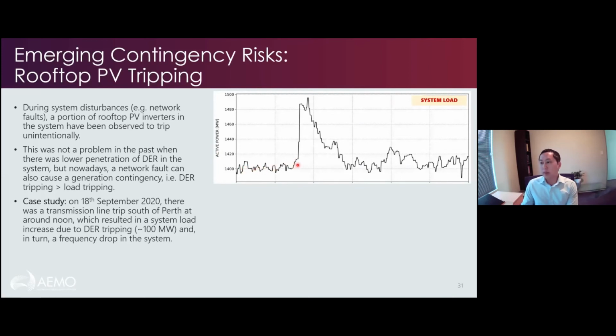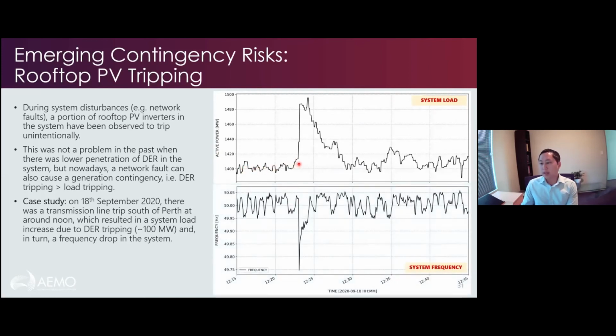We had 1400 megawatts. And here's the system frequency. This is the period of time where the fault occurred. And the transmission line tripped. And we had this load increase due to the net DER tripping. And as a result, we actually had a frequency deviation as well. So you have a network fault that's turning into a frequency contingency.